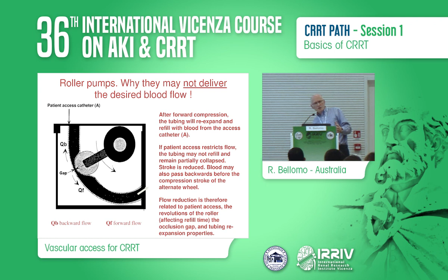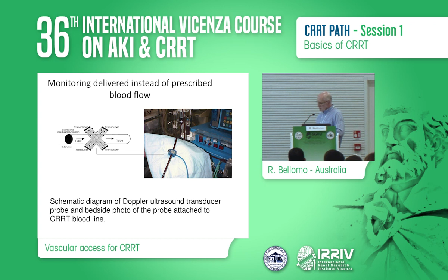One of the things that some of you might believe is that when the pump is set at a particular value, that is the blood that will flow through the circuit. But in fact, that is only measuring the rotations of the cam, and then it calculates the likely blood flow that will come through the circuit. But if you are able to monitor the blood flow with a Doppler flow probe around the tubing of the circuit, you will see that flow is often not quite as much and as predictable as you might think. You will find, for example, that the flow is not steady and continuous, but it has a cycle of systolic pressure and diastolic pressure. And then as the tubing refills, the next cycle gives a kick of flow, and then it goes down again, and it starts again with the cams moving along.